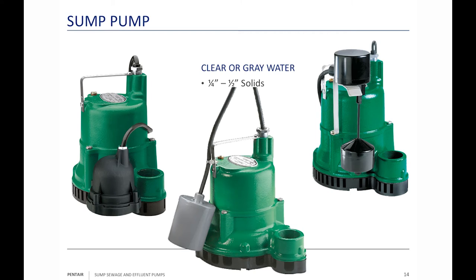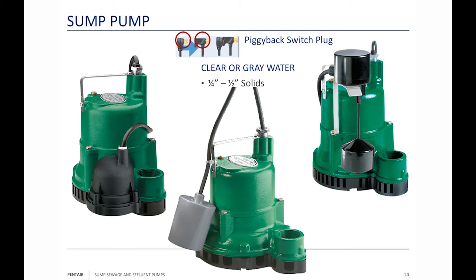Sump pumps are designed to pump clear or gray water — quarter to half-inch solids. I like the piggyback float switch, where you have a float switch plug-in and a pump plug-in: you plug the pump into the back of the switch, then into the wall. If the pump quits, you can unplug the pump from the float switch and plug the pump directly in — if it takes off, you've got a bad switch. Just replace the switch.